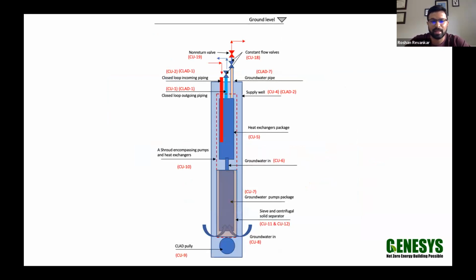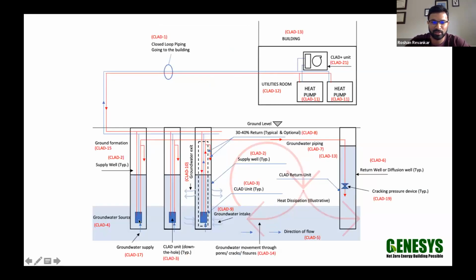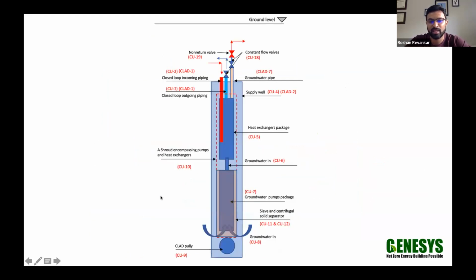So this is a schematic drawing of what the CLAD unit actually looks like. I've always shown those rectangular boxes. Now this is an enlarged version of what this box really is. And in the next couple of slides, I'll show what the device looks like as well. There is supply and return coming in from the building. Here is where all of the heat exchange happens. And there is a third pipe, which is the open loop pipe, which goes into a recharge well.